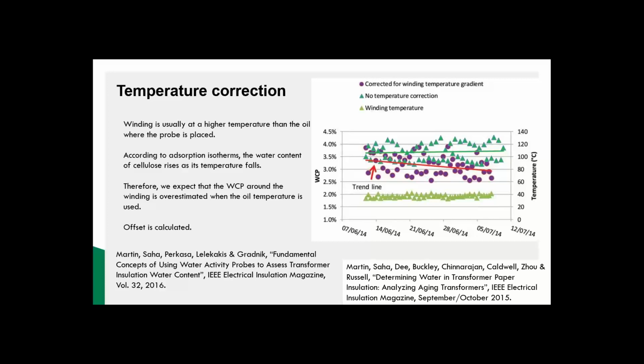And that means, the way the isotherms work, generally, if you reduce the temperature, the water content of paper increases. So what can actually happen when we put the probe into the transformer is sometimes we measure more water in the paper and pressboard than the dielectric response machine does. And this is really just due to the differences in temperatures. So we did go away and think about this, and we looked at how to adjust the temperature and the water activity from the sensor to different temperatures.